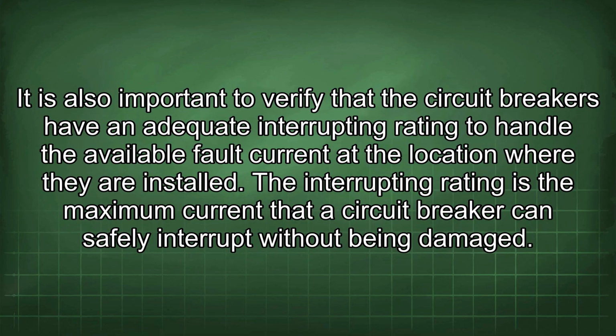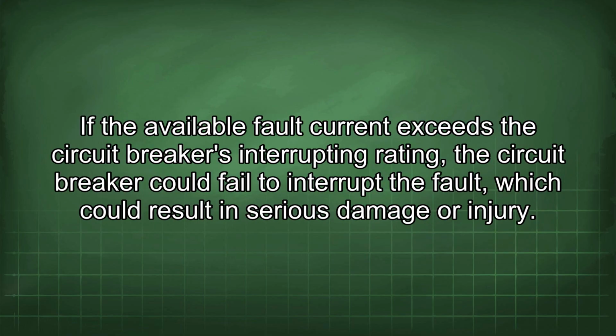It is also important to verify that the circuit breakers have an adequate interrupting rating to handle the available fault current at the location where they are installed. The interrupting rating is the maximum current that a circuit breaker can safely interrupt without being damaged. If the available fault current exceeds the circuit breaker's interrupting rating, the circuit breaker could fail to interrupt the fault, which could result in serious damage or injury.